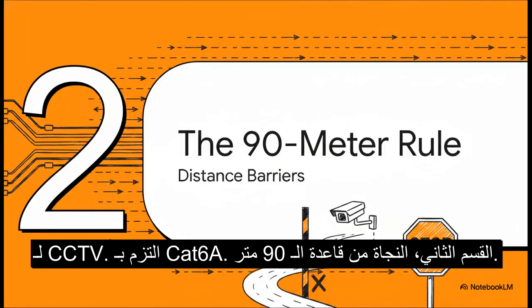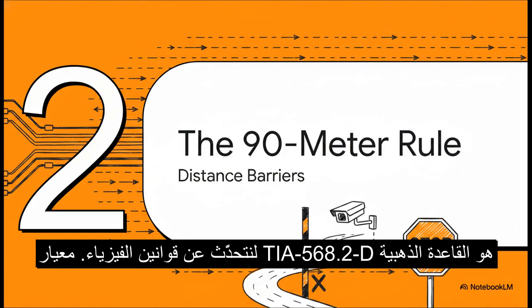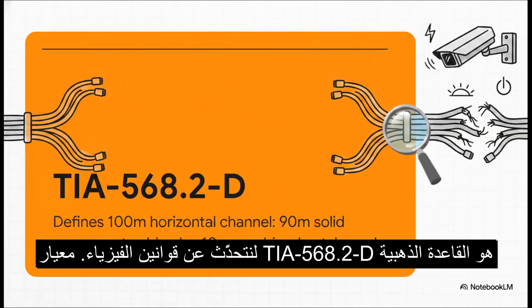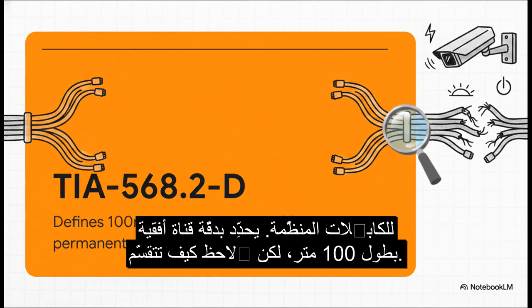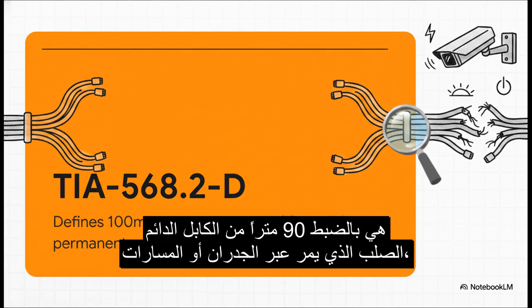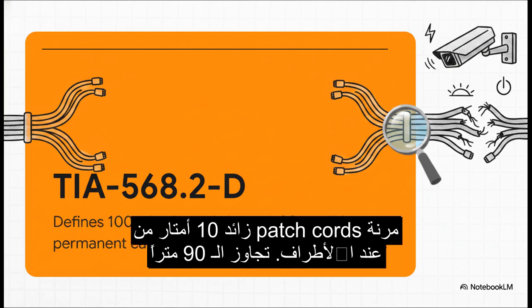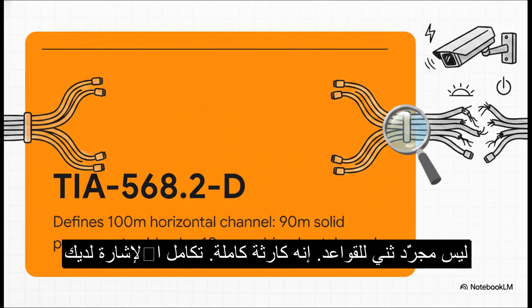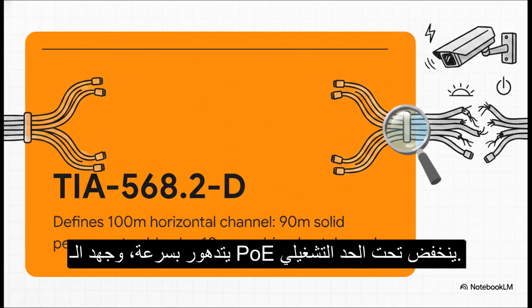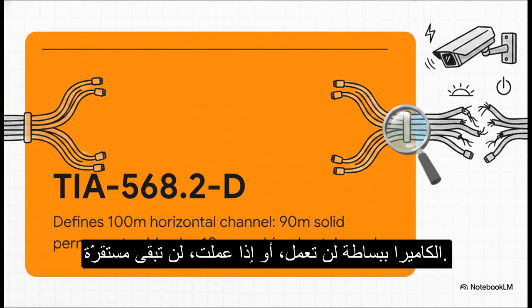Section 2. Surviving the 90-meter rule. Let's talk about the laws of physics. The TIA 568.2-D standard is basically the golden rule of structured cabling. It strictly defines a 100-meter horizontal channel, but notice how that breaks down. It is exactly 90 meters of solid, permanent cable running through the walls or trays, plus 10 meters of combined flexible patch cords at the ends. Pushing beyond that exact 90-meter permanent link, that isn't just slightly bending the rules, it's a total disaster. Your signal integrity degrades rapidly, and your PoE voltage drops right below the operational threshold. The camera simply will not power on, or if it does, it won't stay stable.